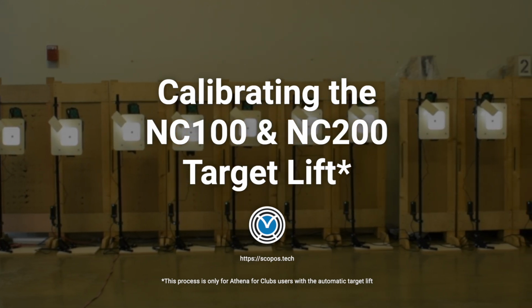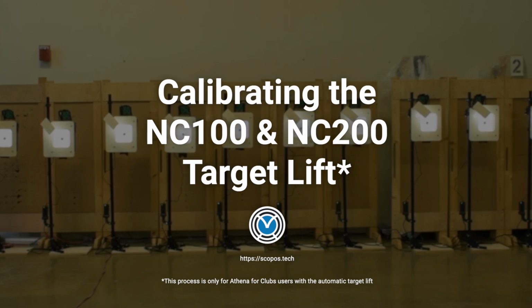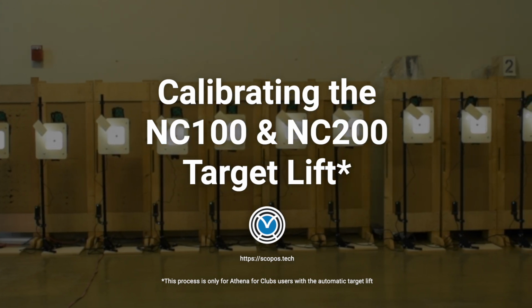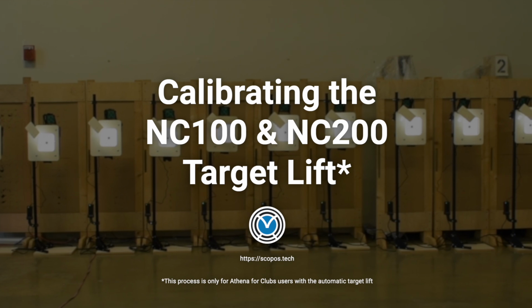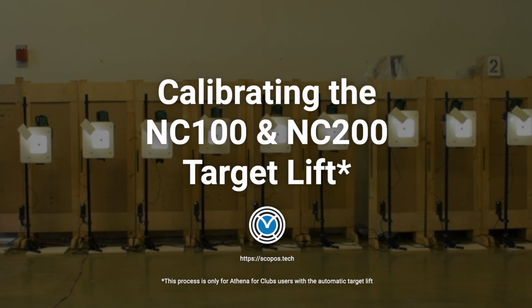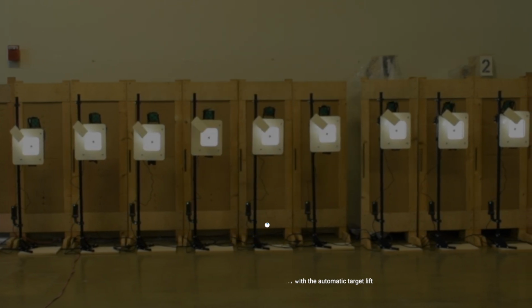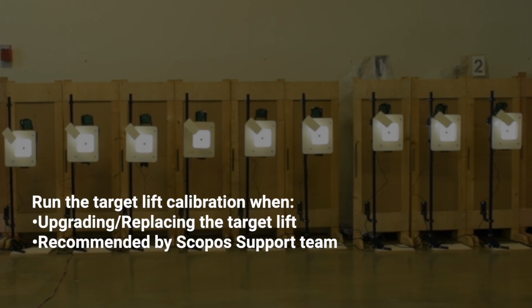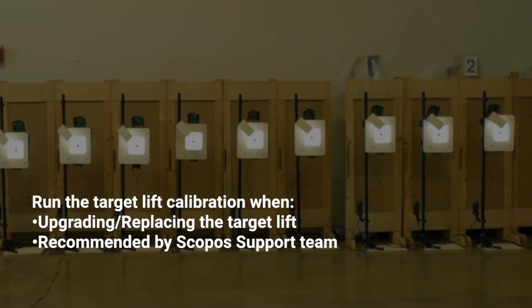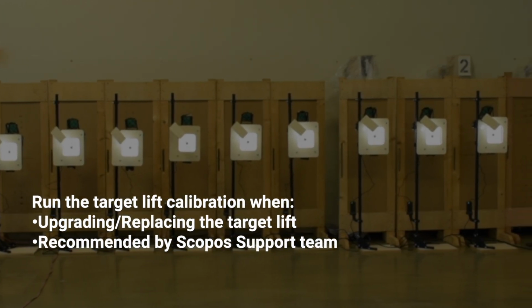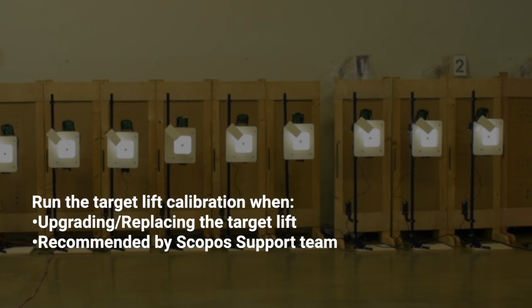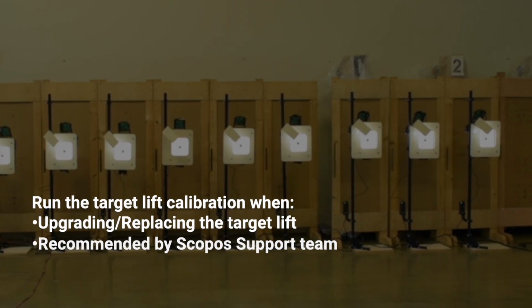The process we will describe is similar for both the older threaded rod and the newer pulley-style target lifts. While the targets are calibrated during the production process, recalibration is sometimes needed for the longevity of the target. We recommend running this process when the target lift is upgraded, or when recommended by our support team. The target lift calibration is not part of our recommended scheduled general maintenance and should be done only when needed.